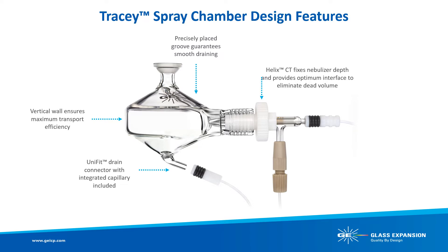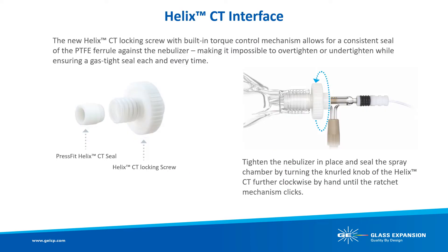All pumped spray chambers include Glass Expansion's Unifit connector and capillary for smooth and efficient draining. The walls of the chamber have a vertical region, which is important for proper aerosol generation and affects transport efficiency to the torch. The Helix CT locking screw and seal uses a constant torque ratchet mechanism to provide a zero dead volume gas-tight seal between the nebulizer and spray chamber for consistent ICP performance.